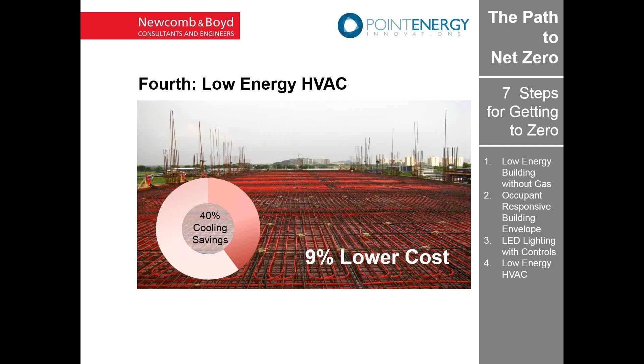Another part of low energy HVAC is friction. A lot of people don't get it, but half the energy in HVAC systems is friction—that's fans and pumps, and they're there to overcome friction. So we're far from optimized. If you look at the human heart, it's 1.5 watts per GPM. It's a measure of efficiency, with 60,000 miles of blood vessels in our body. It's not that the distance is so short—there's so much going on in our body. The heart's very efficient. But when we do HVAC systems, we're typically in the 15 to 20 watts per GPM range.